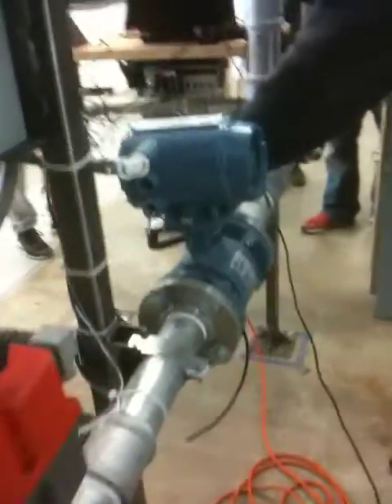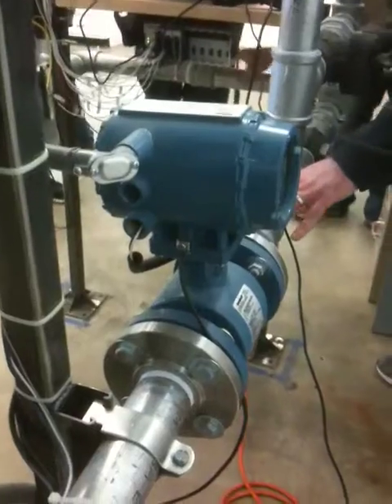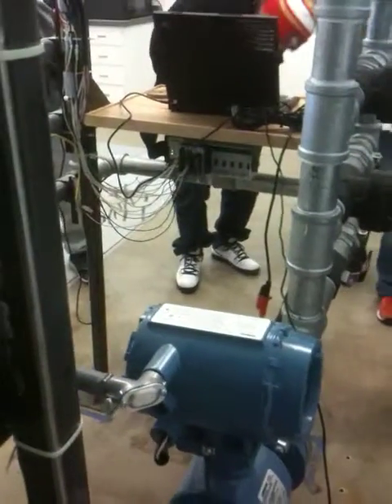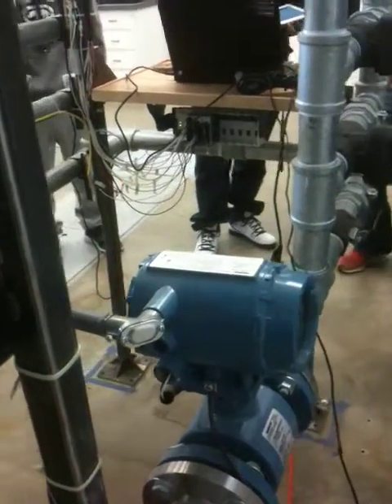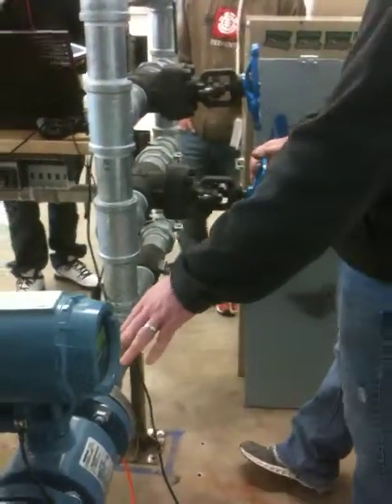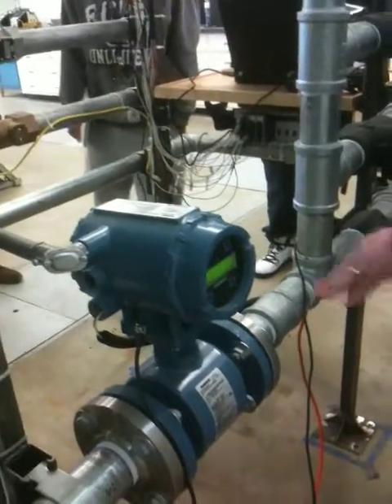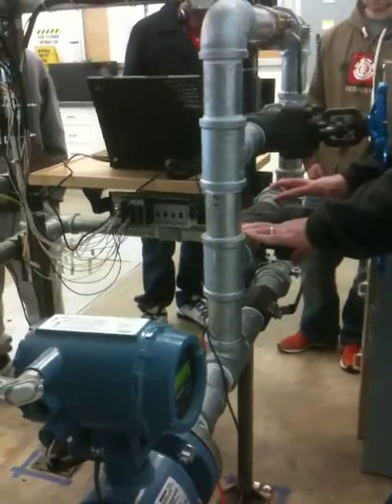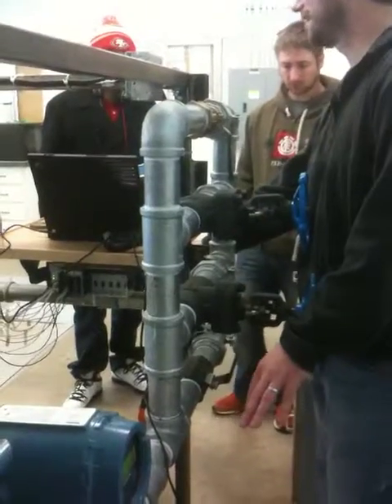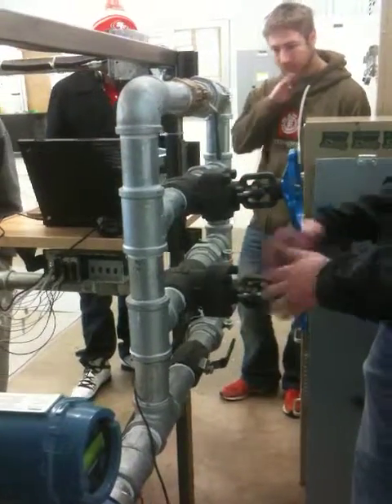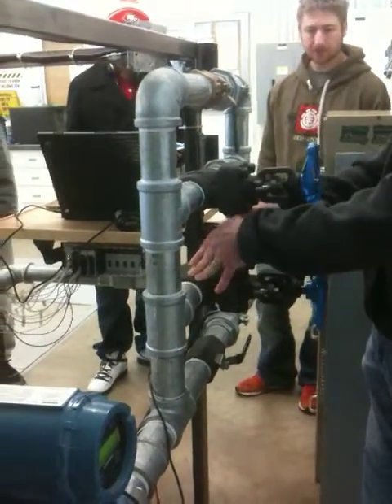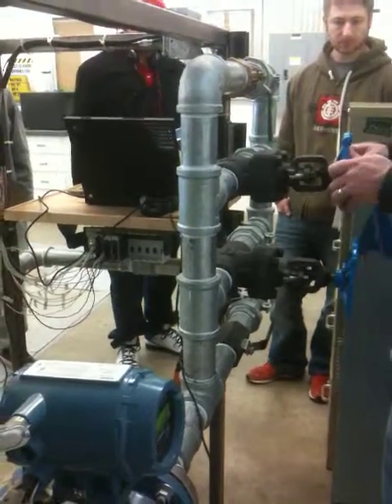One thing about these, we'll measure the pressure right here and the pressure under there. And so when you try to isolate, say, to get the pressure drop through this gate valve, the flow is going to come in here. Basically treat this like an elbow. It's going to come up here, go here, it's going to go way down, it's going to go through there. So you want to sort of subtract out the pressure loss through each of these things in order to isolate just the pressure loss across this. So there's that part of it.